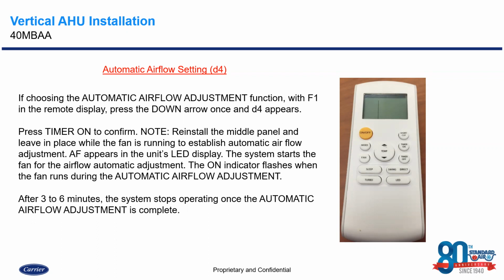Once you hear that audible beep, you know that command was sent to the unit, and then what you're going to see next is this fan slowly start up. And once you see the fan slowly starting up, you want to put the cover back on the air handler itself to make sure that it's not open and sucking return air from the space around you, because the system is essentially going to try to balance itself out and figure out the static pressure that it needs to operate at to ensure that it's getting good airflow to all of the zones that are on this system.